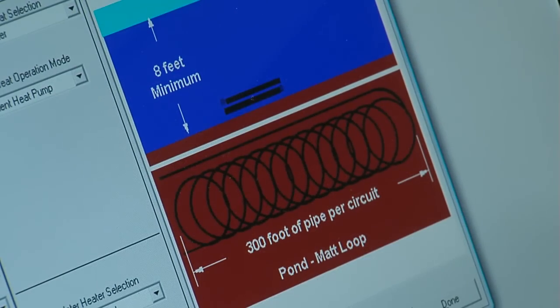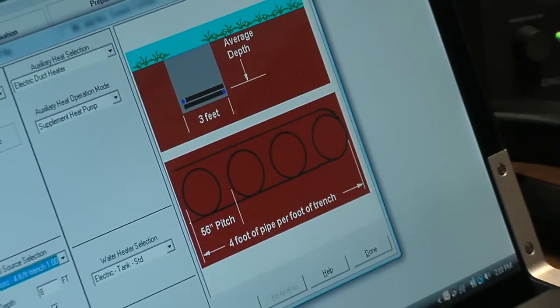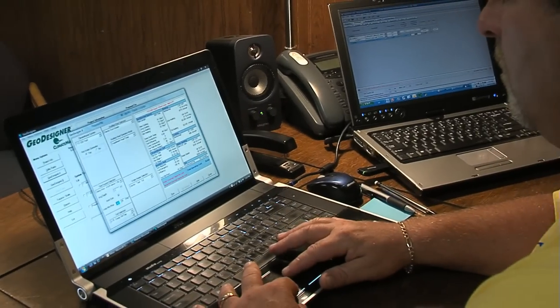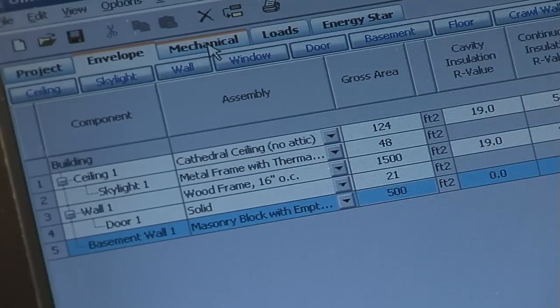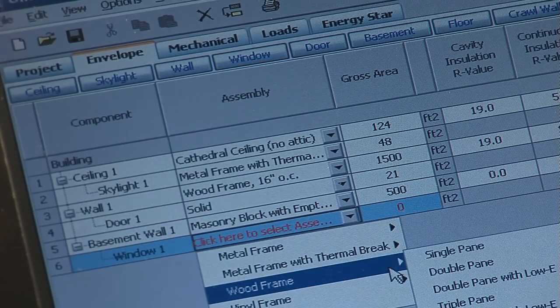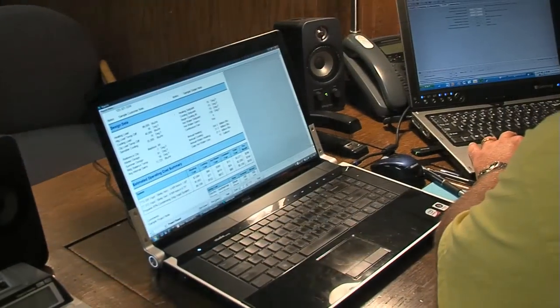Cooling is not so much of a concern, as the geothermal heat pumps today have 2-stage compressors, where first stage will operate at about 2/3 of the full capacity when needed. If more air conditioning is needed because of the load, then second stage will engage and you will get 100% cooling with the geothermal system.